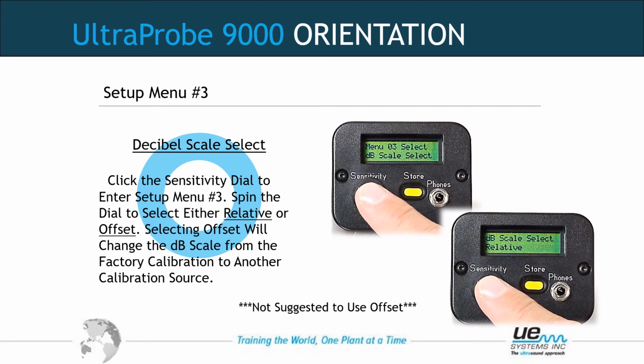But if we were using an Ultraprobe 401 grease caddy with a magnet to lube our bearings, which we can load a route to that digital unit, and we were scanning the bearings normally on route with the 9000 and a stethoscope module, we would obtain different readings between the two units with different modules. So you would position the 401 grease caddy on a spot on a motor bearing or a bearing and obtain a reading. And if it read 50 dB, that's fine. You pick the same spot with the Ultraprobe 9000 and obtain the reading. Let's say it says 42 dB. We are a difference of 8 decibels.